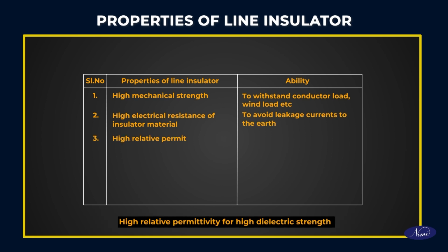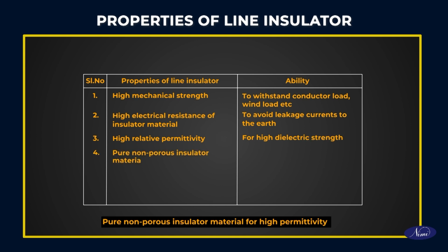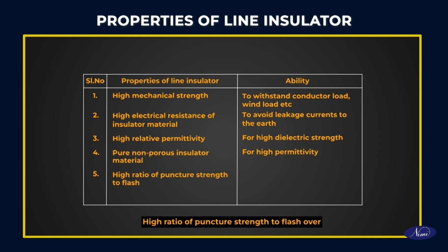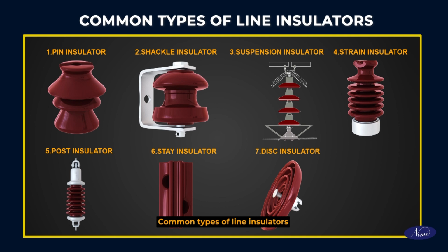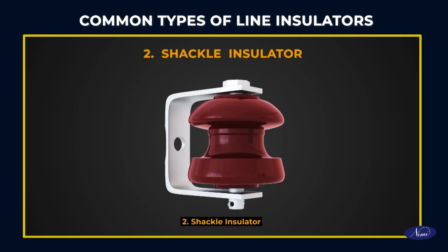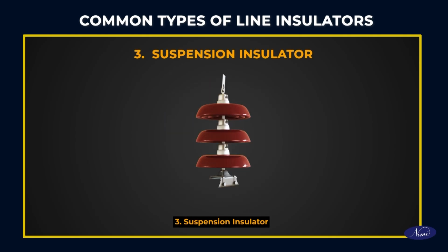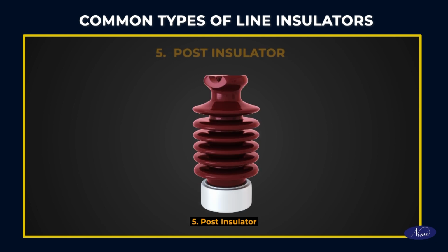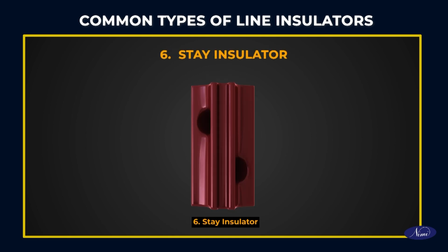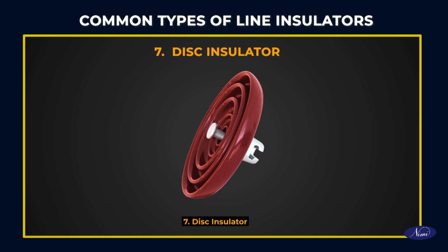High relative permittivity for high dielectric strength. Pure non-porous insulator material for high permittivity. High ratio of puncture strength to flash over, to withstand flash over voltages. Common types of line insulators: pin insulator, shackle insulator, suspension insulator, strain insulator, post insulator, stay insulator and disc insulator.